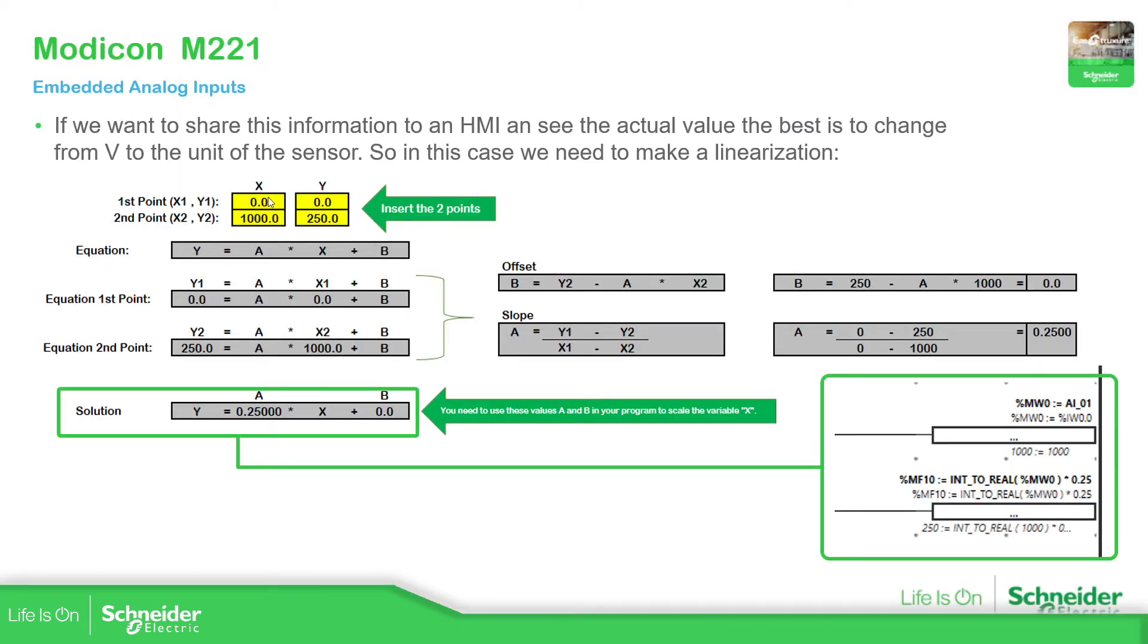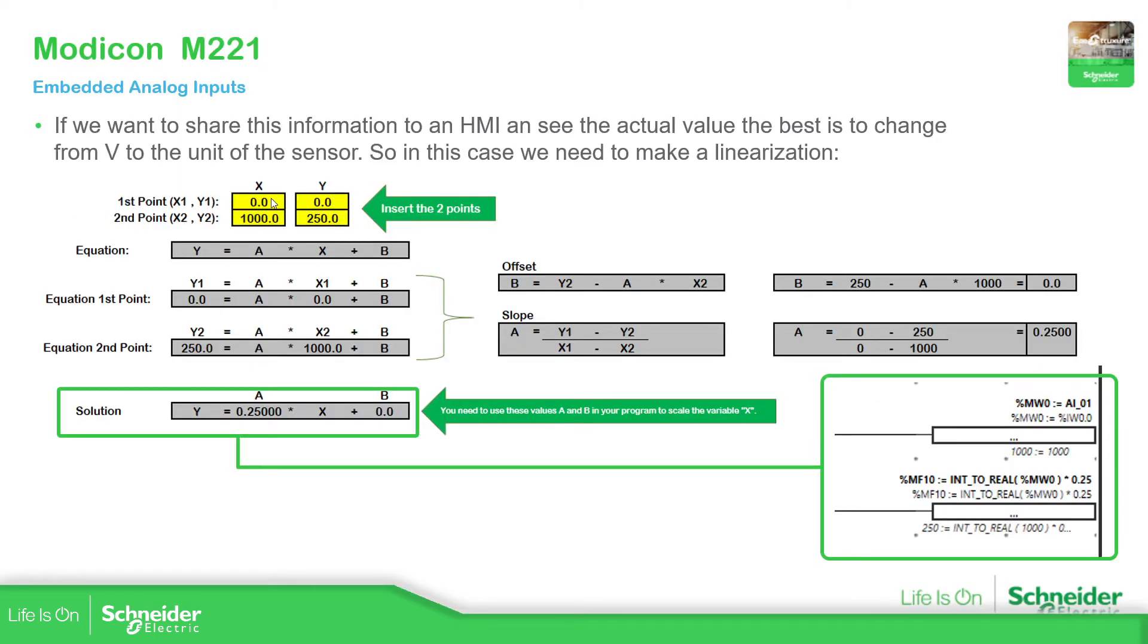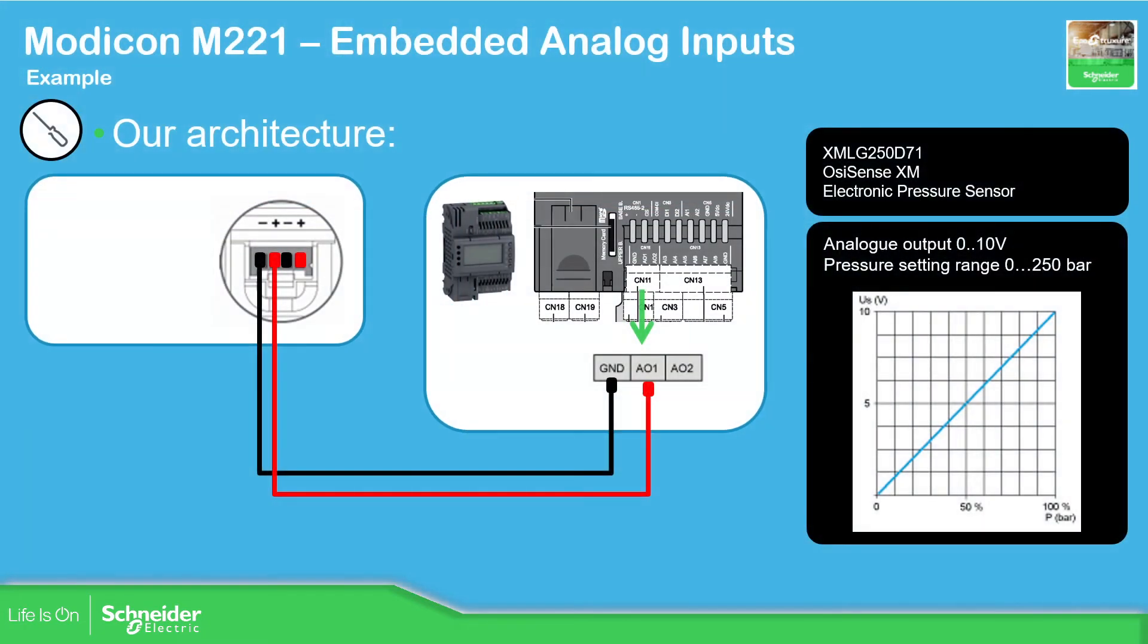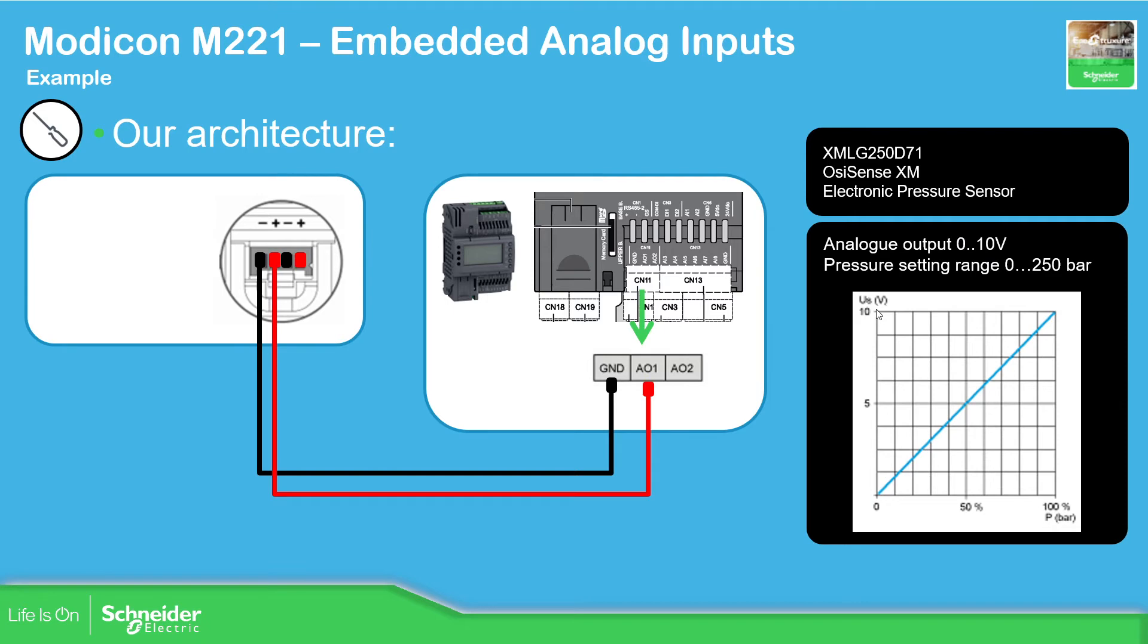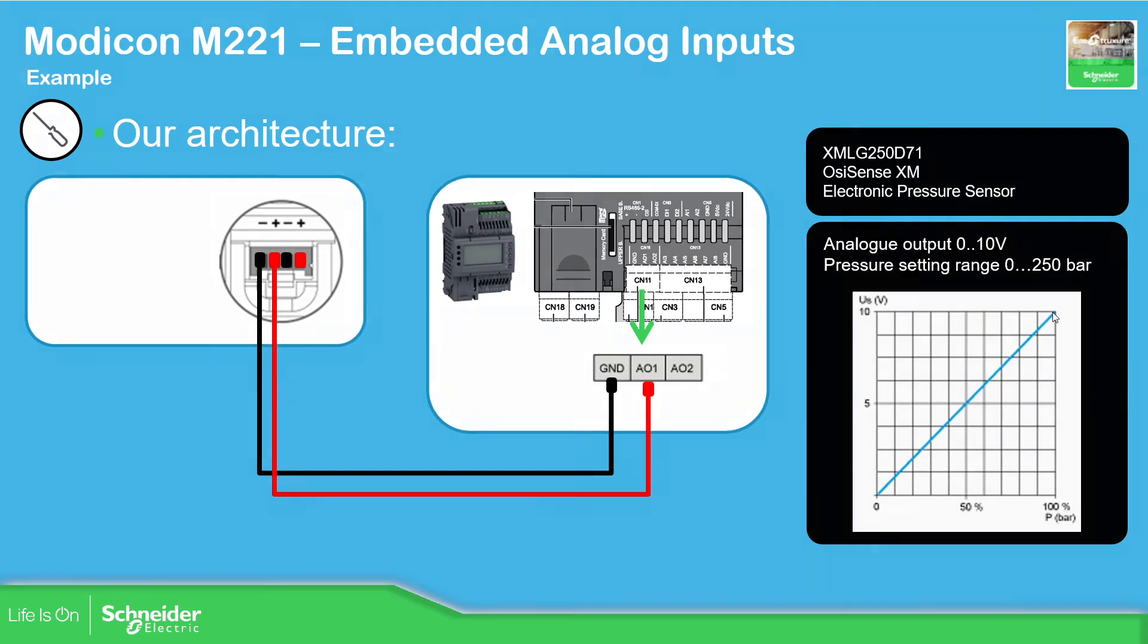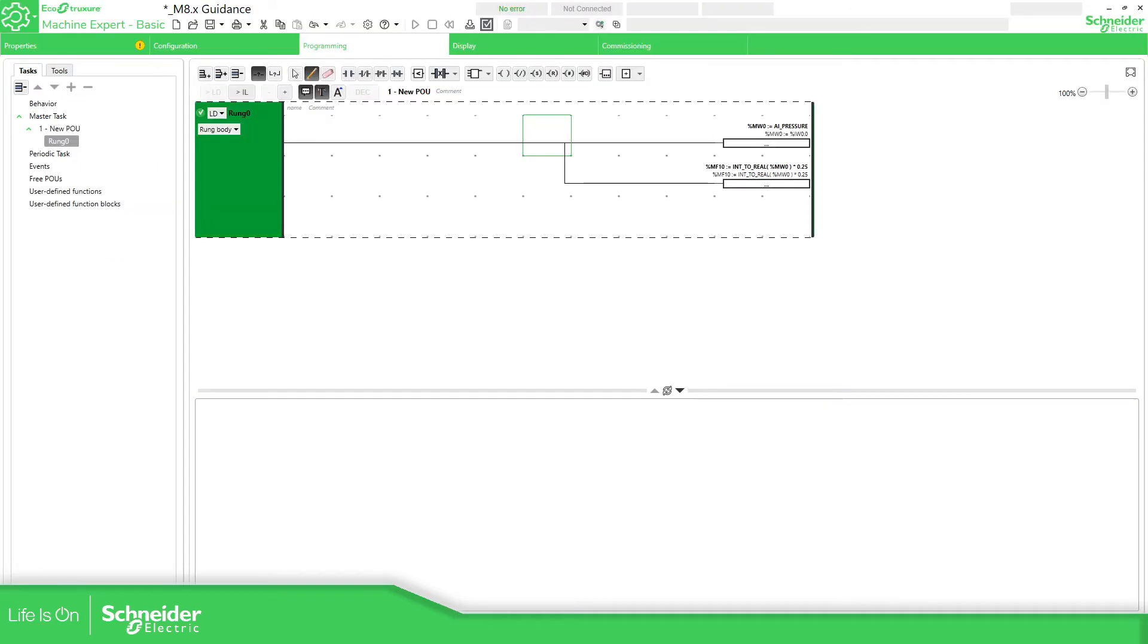This is calculated in here. I have the two points for my graphic. So I'll show you in here. The starting point is 0,0, and the other point is the 100% that in my case would be the 250 bars, and here is the 10 volts. That would be my raw value. And my raw value is 1000. That's why I use these two points to calculate.